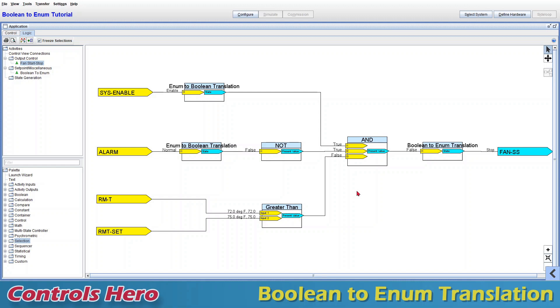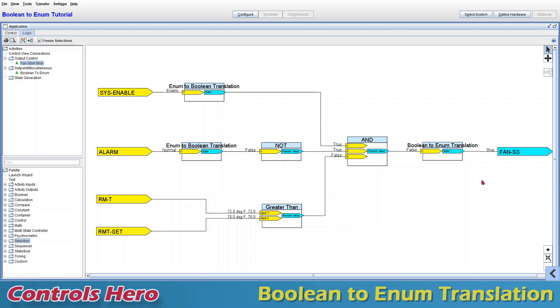Those are logical boolean conditions. It reads like this: if my system enable is enabled, and my alarm is not an alarm, and my room temperature is greater than my room temperature setpoint, then start the fan. Notice that we have our translation here because our logical conditions are in boolean format — false, true, true, false. Boolean is two states: true and false. Fan commands usually have units of stop/start, off/on, or disable/enable.